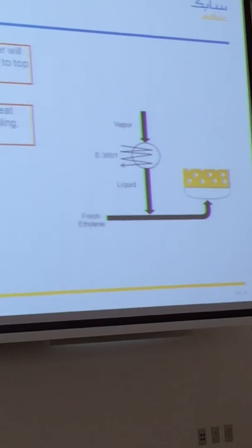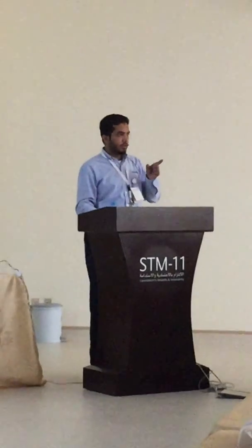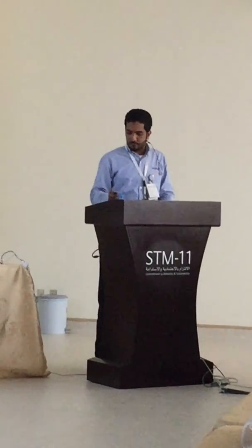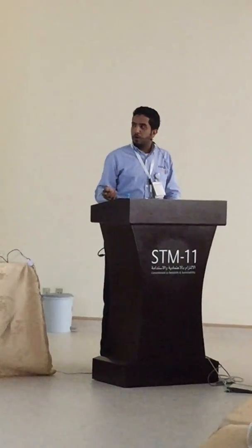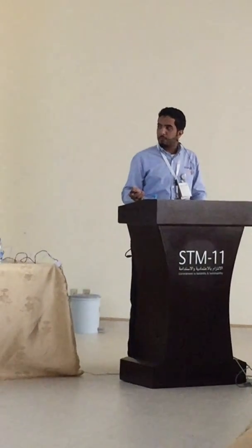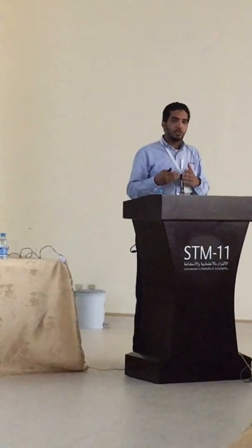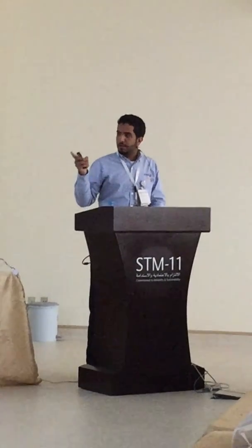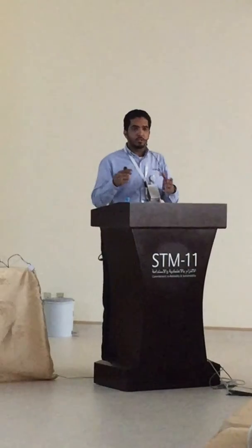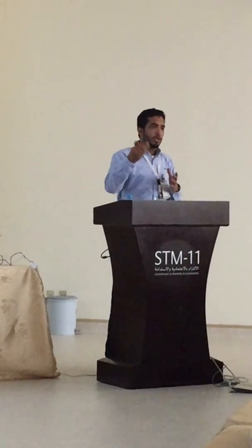That will reduce the duty of this heat exchanger, because fouling will form a layer which will reduce the duty. And since we have only single line equipment in the LAO plant, we need to go for a cleaning shutdown in order to clean this heat exchanger and go back to the normal heat transfer coefficient. That means we don't have any bypass or any other heat exchanger in order to do the same job.